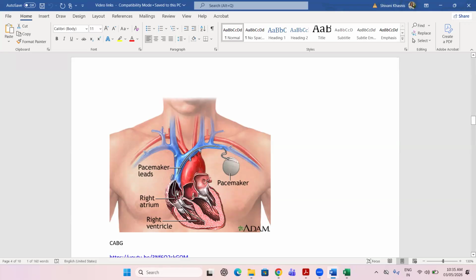But what if there is only one lead, one electrode? You don't need two electrodes, you need only one electrode. Then you call it a single lead pacemaker. So single lead, dual lead, or multi-lead pacemaker will be there. In a multi-lead pacemaker, usually more than two leads will be there. Three or more, but usually three. So then you call it a multi-lead pacemaker. So depending on how many leads you use for a pacemaker, the pacemakers are classified into single lead, dual lead, or multi-lead pacemakers.